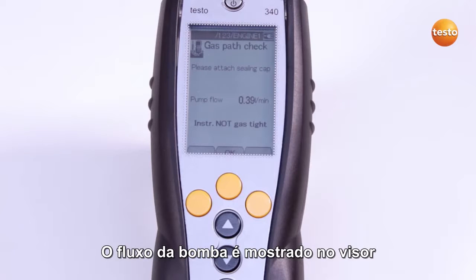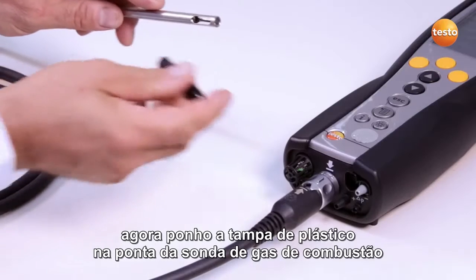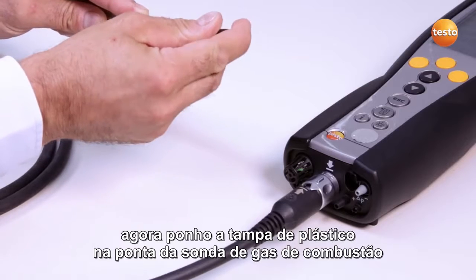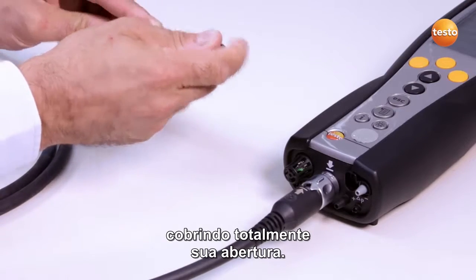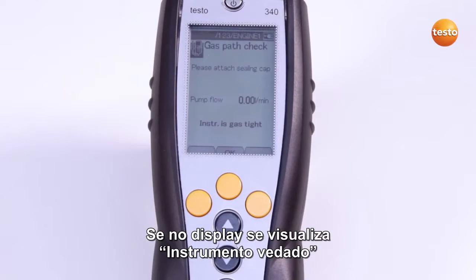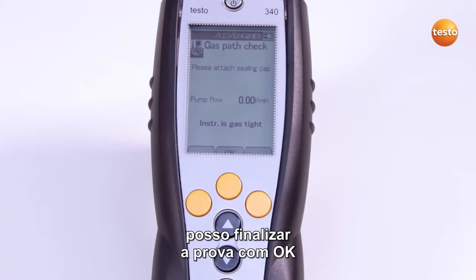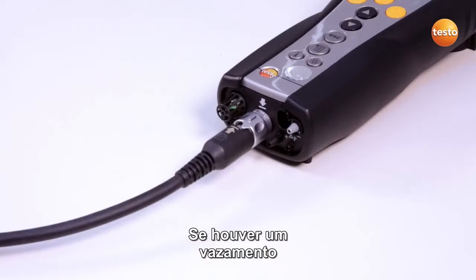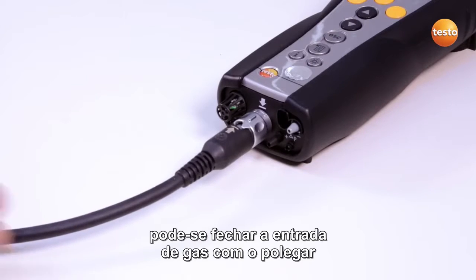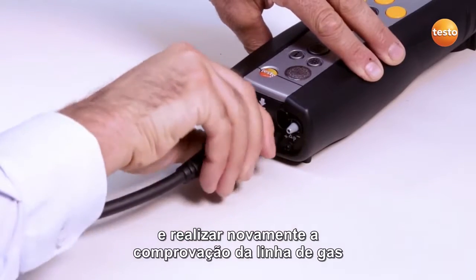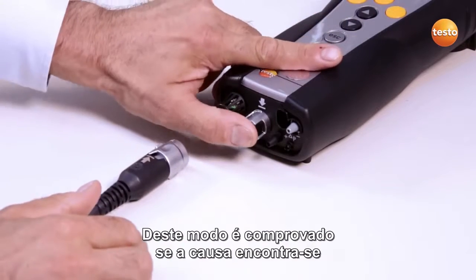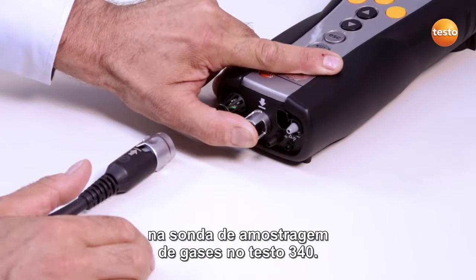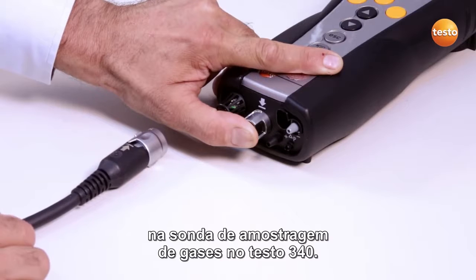The pump flow is shown on the display. Now I put the plastic cap on the tip of the flue gas probe so that its opening is completely covered. If Instrument is gas tight appears on the display, I can finish the test by pressing OK. If there is a leak, you can seal the gas inlet using your thumb and carry out the gas path check again. This enables you to check whether the cause is the gas sampling probe or the Testo 340.